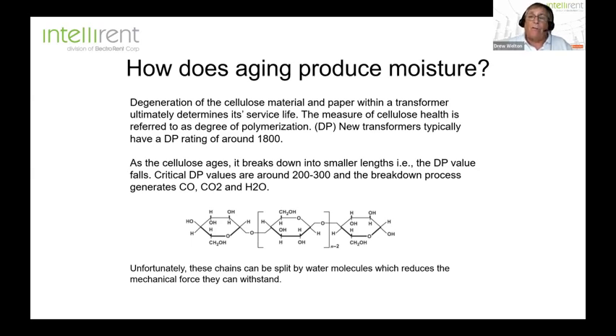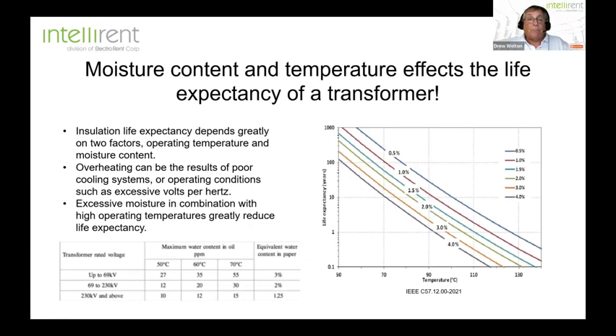Well, as the transformer starts to age naturally, the resin bonds surrounding the insulation start to break apart and degrade as your degree of polymerization goes down. When these resin bonds and molecules split, the byproduct is moisture, is water. So even though you've never exposed that transformer to outside moisture, it can generate moisture through its natural aging.